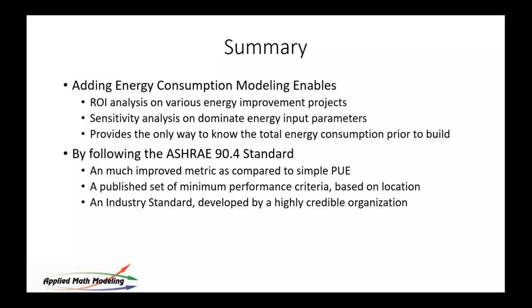So what this kind of modeling allows you to do is things like ROI. What did it cost to do those improvements I just made? Now, I did cold aisle containment. How much does cold aisle containment cost? I don't know exactly because I'm not in that business, but it's easy enough to find out. You get quotes on it, but at least now you know what the return is and how long it will take to return it. At $10,000 a year, the chances are you could return it in a few years, which is usually within the scope of reasonable for energy projects. And it also is the only way to know the total energy consumption prior to your build.